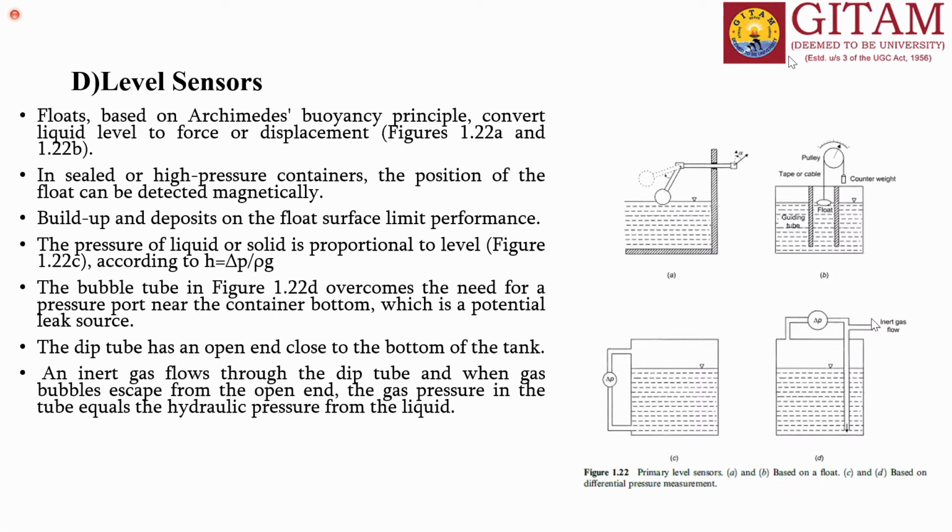How much pressure this inert gas is experiencing because of the liquid stored in the tank gives us the amount or the volume of the liquid in the tank. We have to allow inert gas to form bubbles, and depending on the pressure experienced by this inert gas to form bubbles, that will give us the volume of the liquid in the tank.